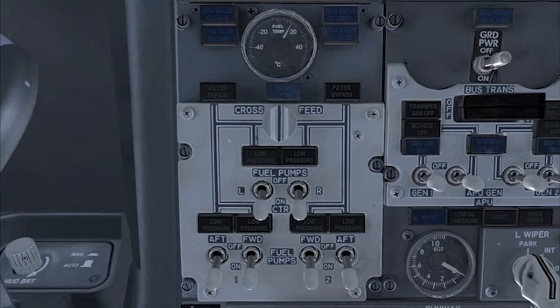When the switch is rotated either open or closed, 28-volt DC power travels through a switch assembly to the actuator. The valve is then moved to the appropriate position. When opening the valve, the open light located above the knob temporarily illuminates bright as the valve transitions, indicating a switch position disagree. When opening of the valve completes, the light will dim, indicating that the valve is fully open.